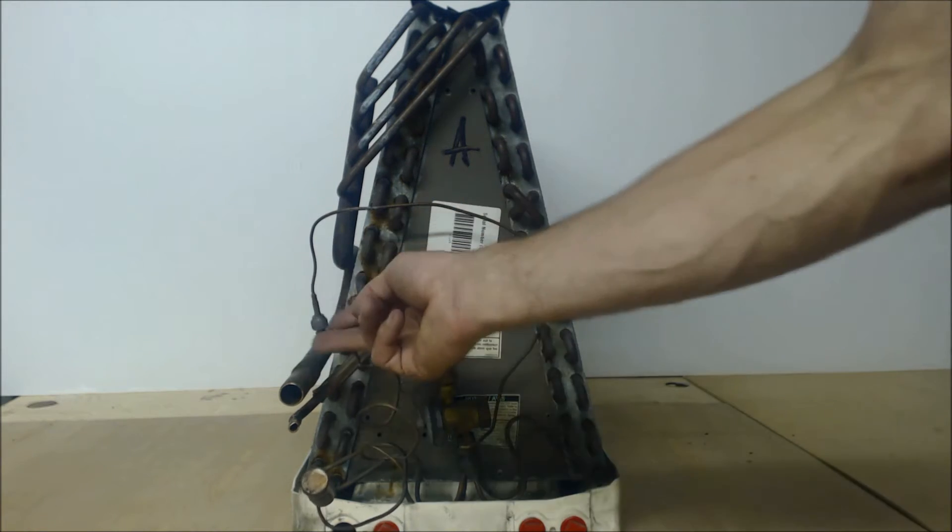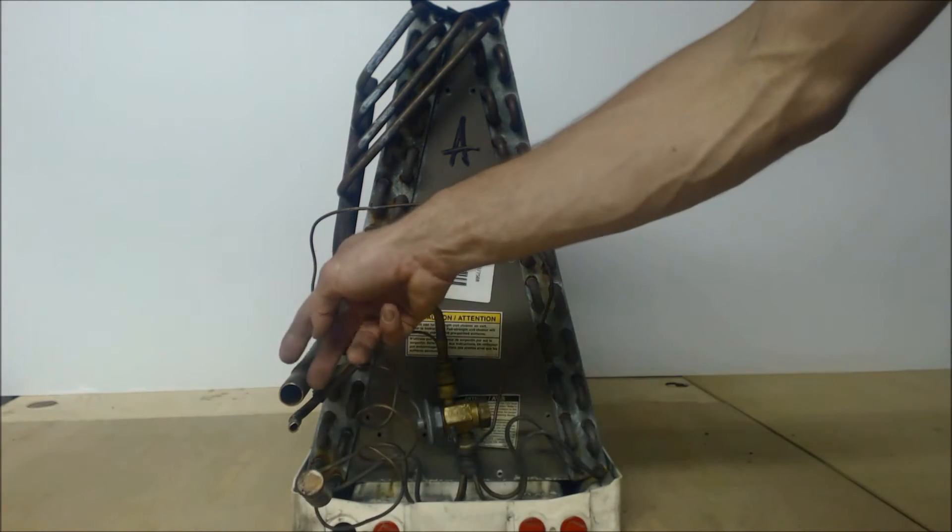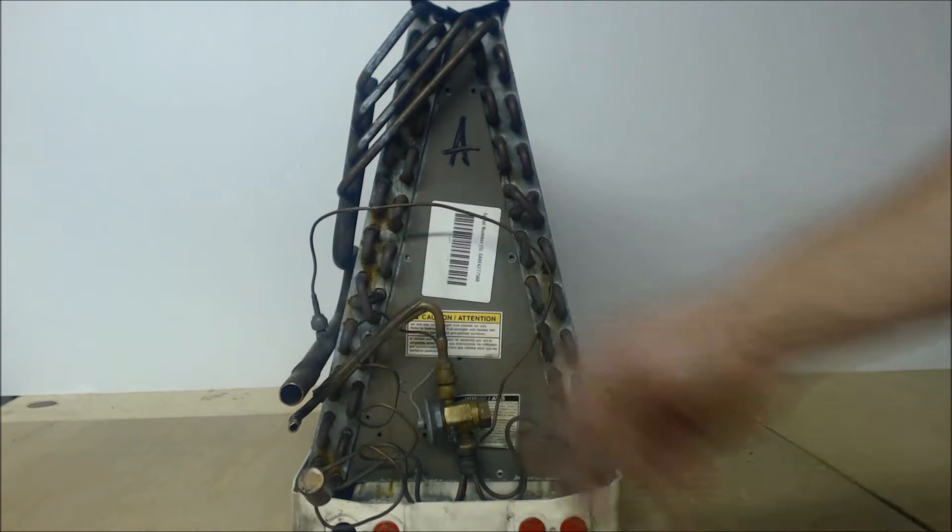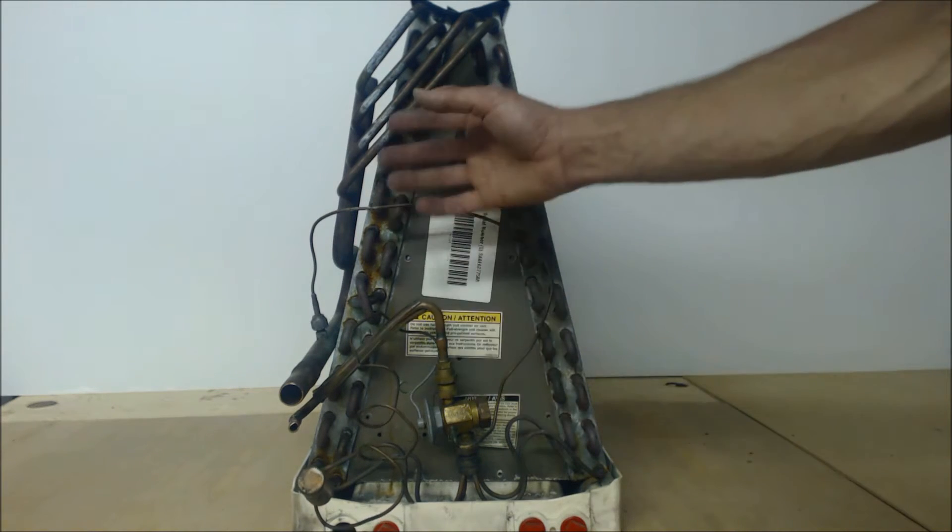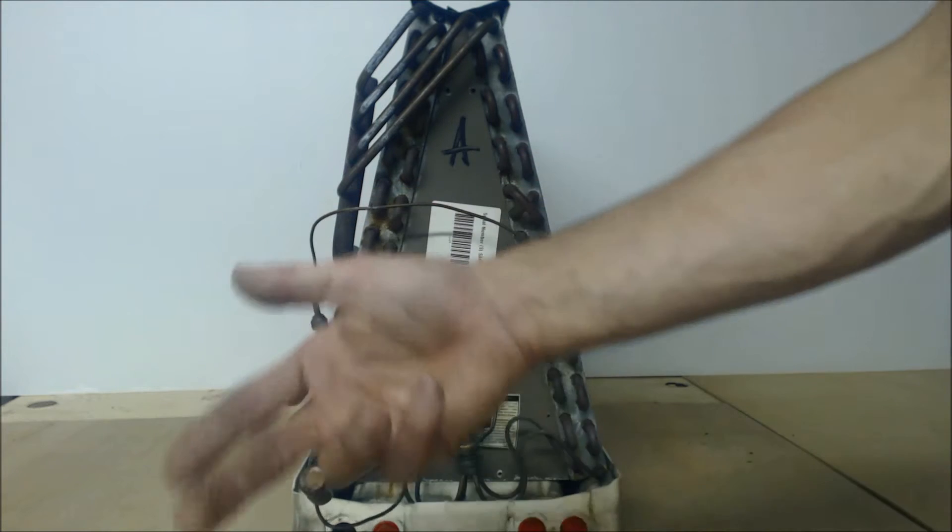Say it came out of here at only 6 degrees superheat. By the time it got to the compressor, maybe it lost its superheat. You know, it could have gained it, but maybe it lost it. So if it did, then that has a chance to turn into a liquid.